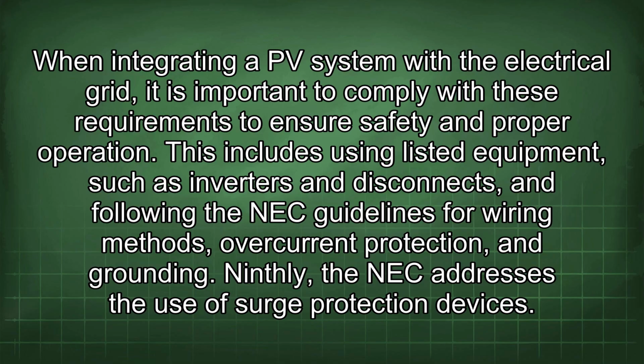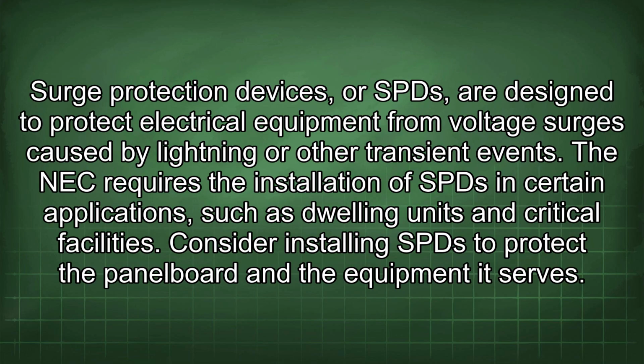Ninthly, the NEC addresses the use of surge protection devices. Surge protection devices, or SPDs, are designed to protect electrical equipment from voltage surges caused by lightning or other transient events. The NEC requires the installation of SPDs in certain applications, such as dwelling units and critical facilities. Consider installing SPDs to protect the panel board and the equipment it serves.